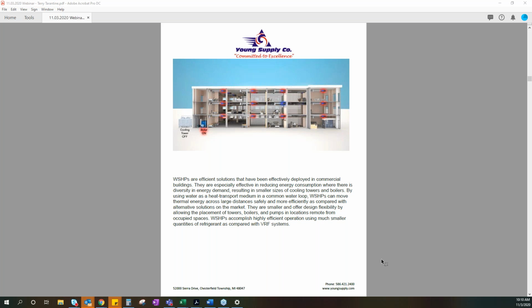At this point, what we're doing is taking typically internal spaces where we're needing air conditioning, and we're transferring that heat via the water, or in a VRF system it would be via the refrigerant, to the outer zones where we need heat. So now we're not buying energy, we're just transferring the energy around the existing building envelope. So this is where a lot of the system design is coming in.